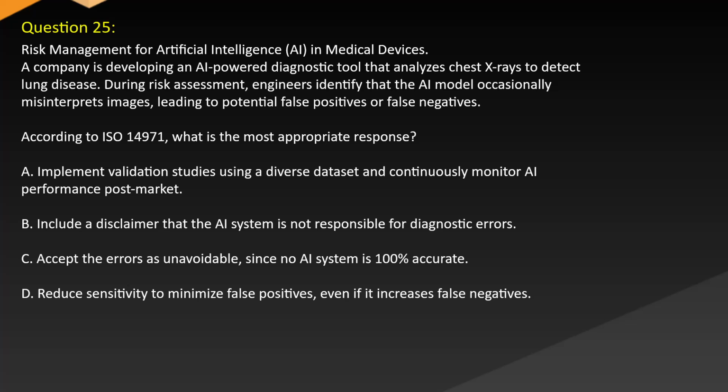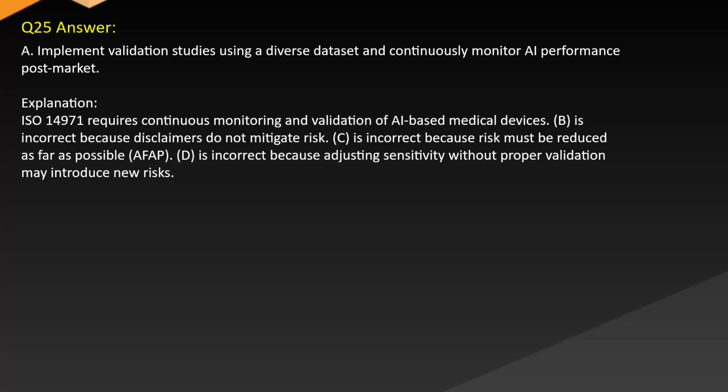Answer: implement validation studies using a diverse dataset and continuously monitor AI performance post-market. Explanation: ISO 14971 requires continuous monitoring and validation of AI-based medical devices. B is incorrect because disclaimers do not mitigate risk.